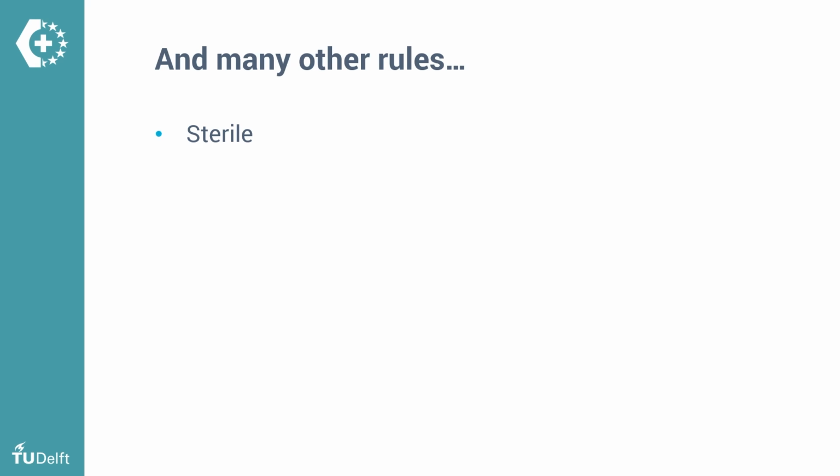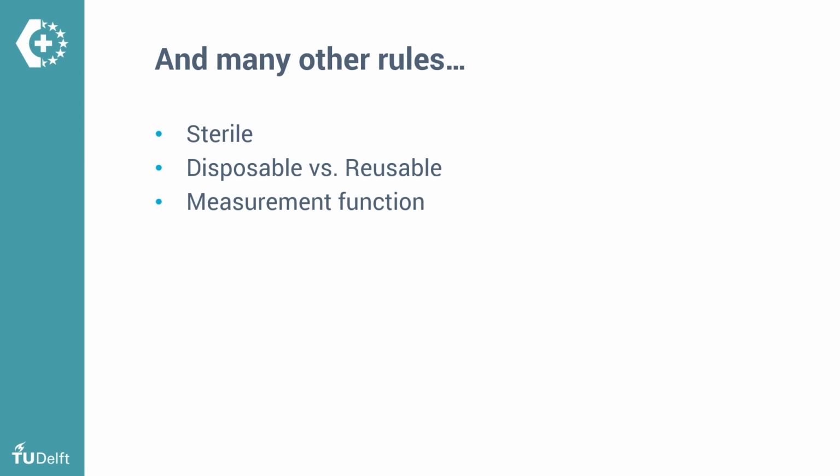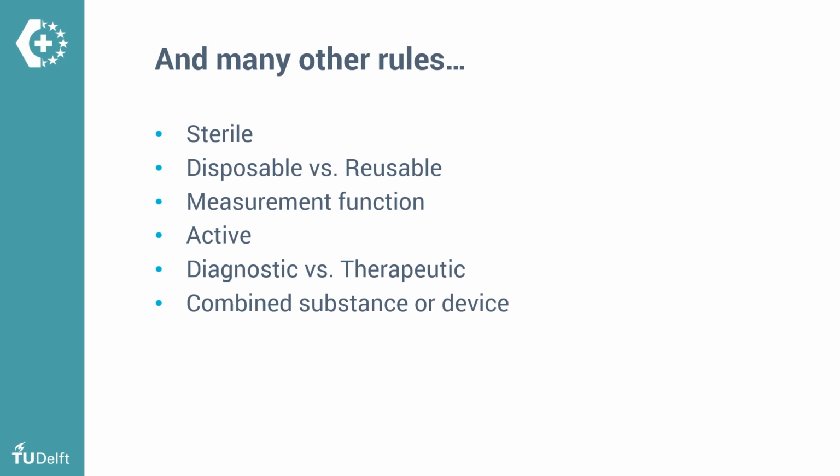Should the device be sterile? Will it be disposable or reusable? Because in the latter case, it must also be cleanable. Does it measure something important or perform some energetic action? Is it meant for diagnosis or also for treatment? And will it be used in combination with some kind of substance or other device? If there are several of these rules that apply, it's always the strictest rule, leading to the highest risk classification, that counts.